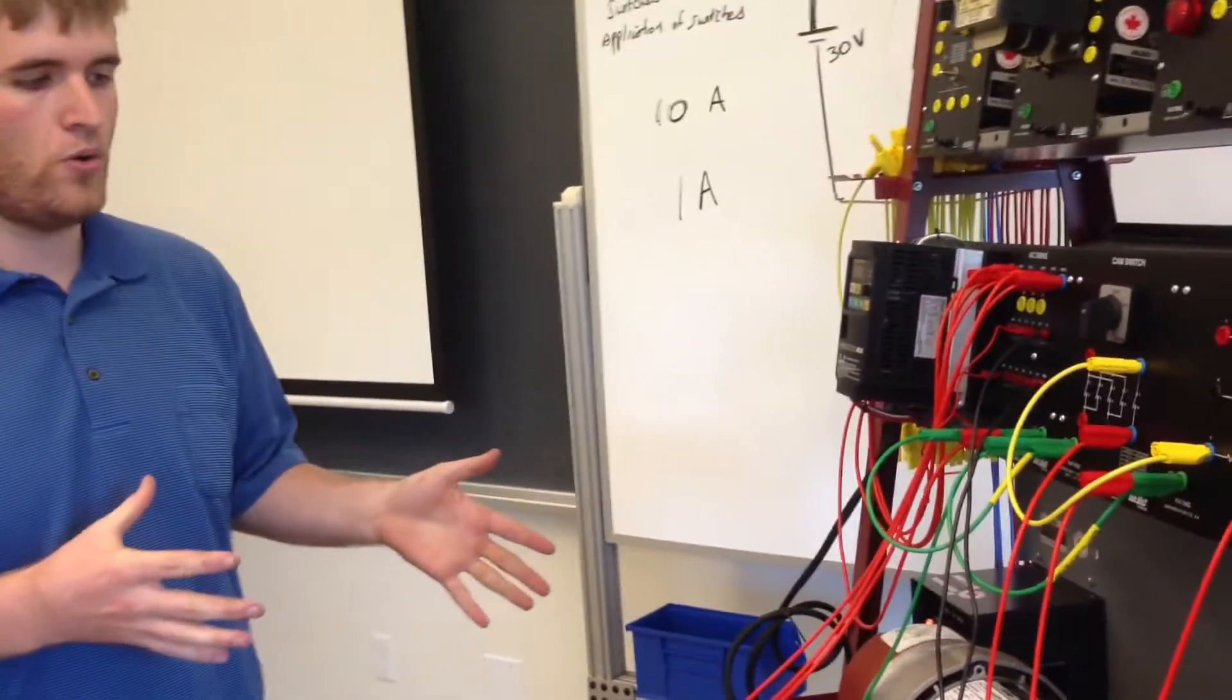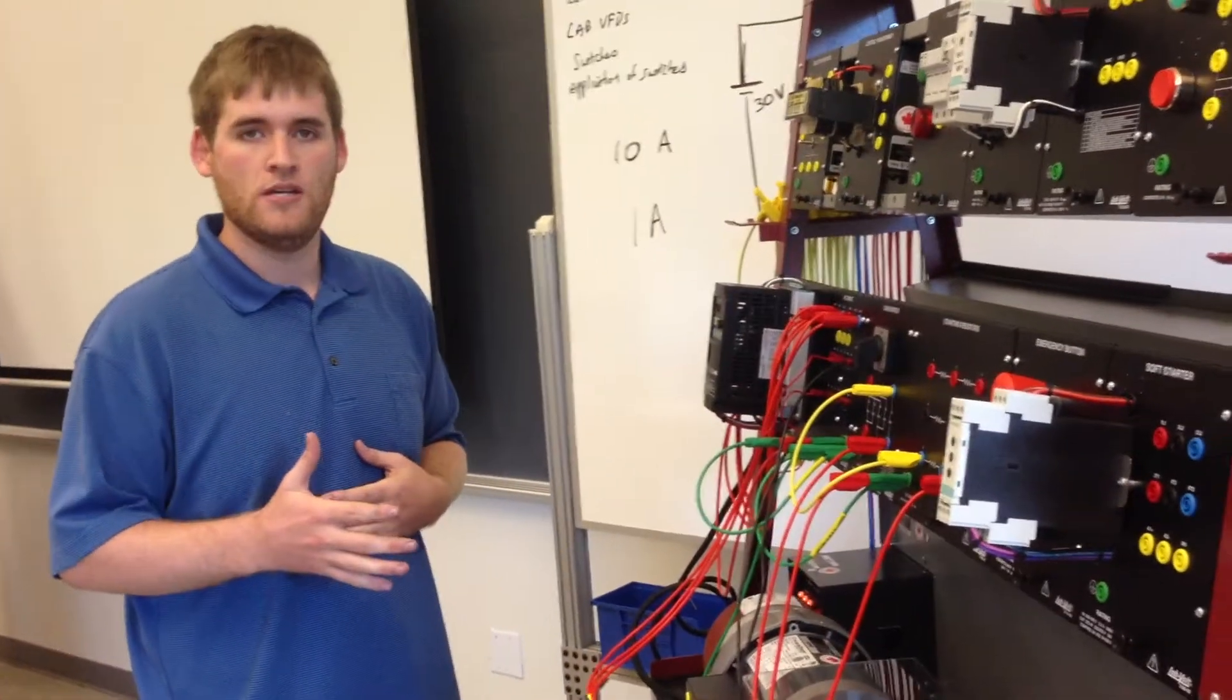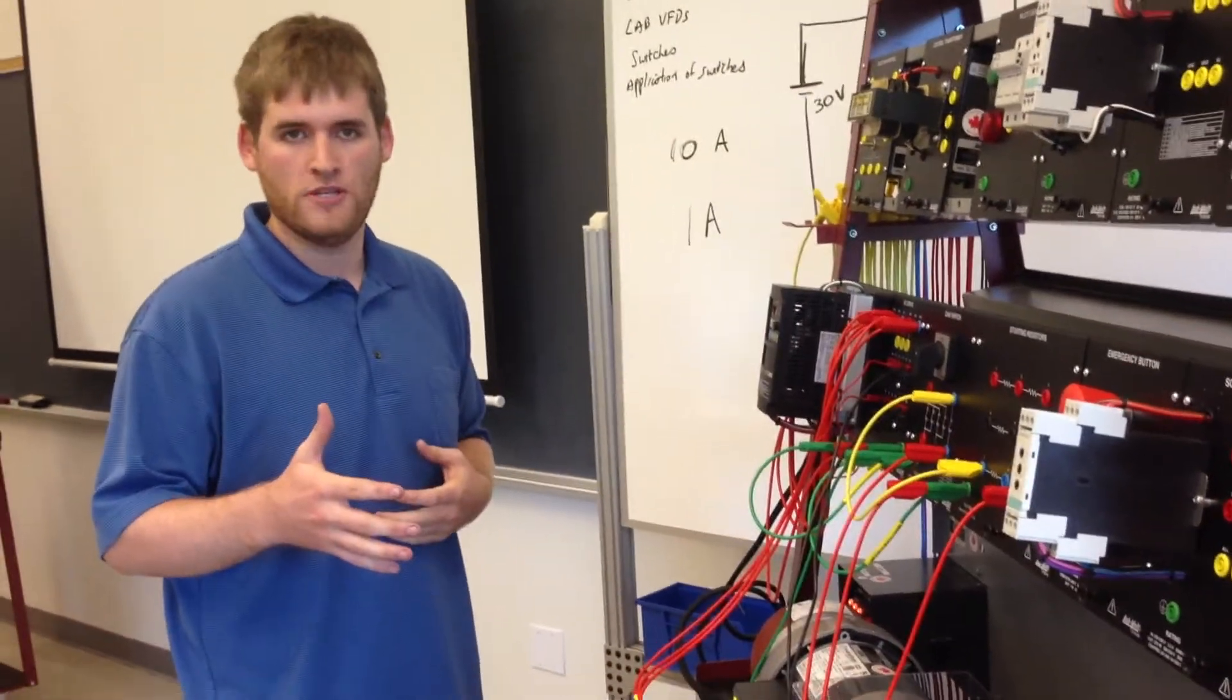Like I said, it's already set up. So when I'm running it without this load on the DC motor, it's going to go into normal operations. When I add this load on the DC motor, it's going to trip our overload limit, and it's going to scale the motor speed to match whatever I have my overload limit set at.